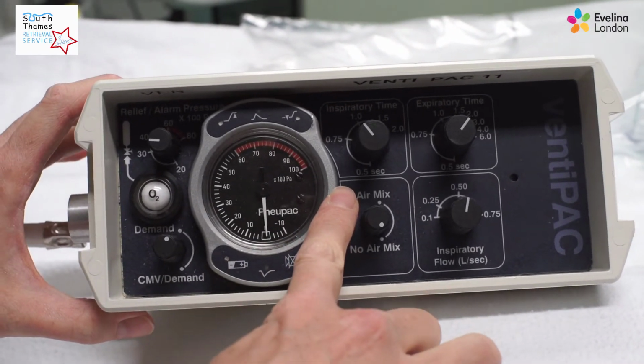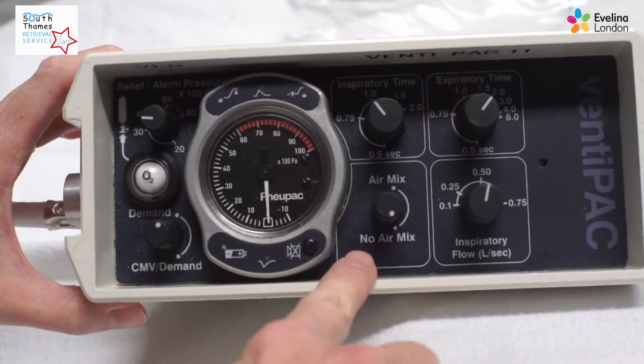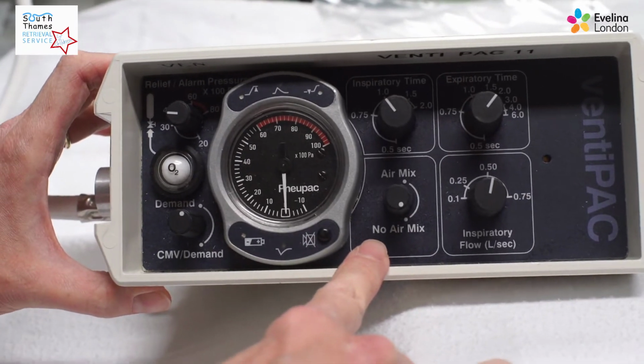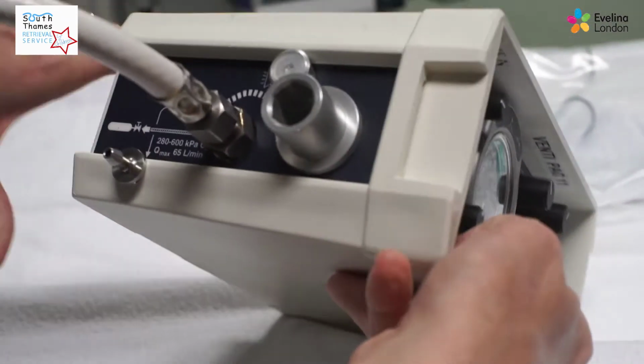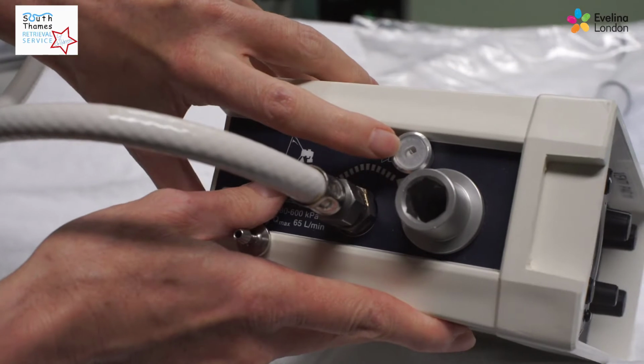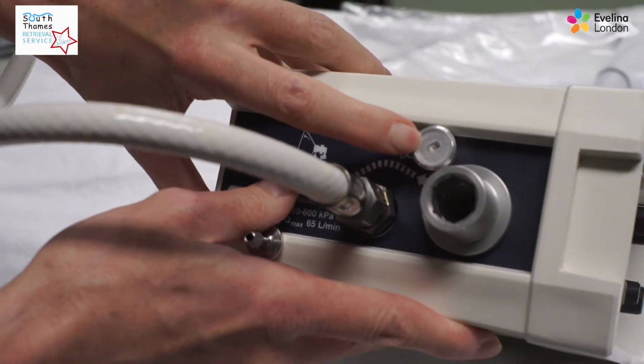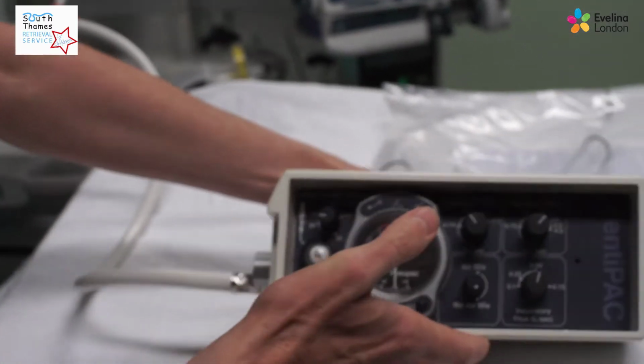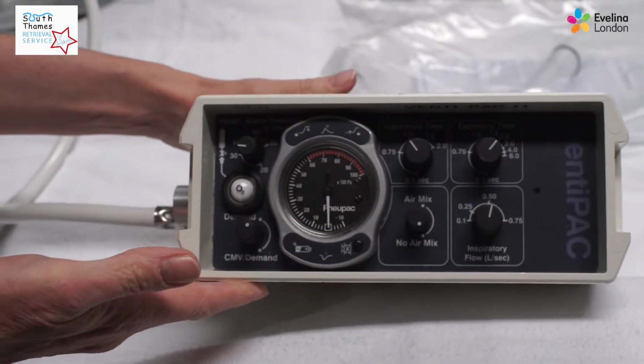We can either deliver 50% air mix or 100% no air mix. For the air mix, air is entrained from the room from this device. As always, we check the ventilator hasn't been damaged or dropped and that the screen is flat.